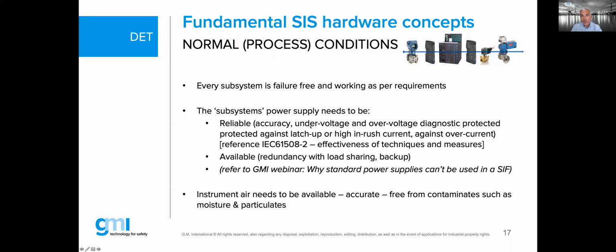It's all about the undervoltage and overvoltage diagnostic protection against latch-up or high inrush current, or against overcurrent. All those items are specifically described in the hardware development section, part 2 of the 61508 edition 2, which is a 2010 release. That's what we say over here. That's also measured in the effectiveness of the techniques and measures used to try to avoid and to control those types of failures.